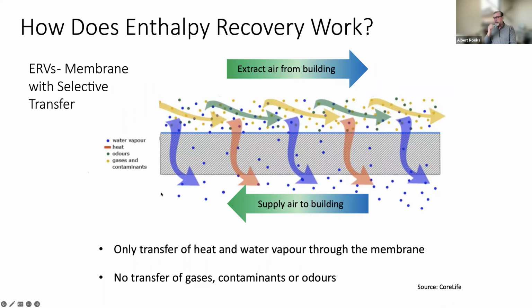The way the enthalpy recovery works is just like a Gore-Tex jacket. Upper right, we've got extract leaving the building. The extract is coming from the kitchen or bathroom, so it's got a slightly elevated humidity level, and the supply air to the building is dry coming in. And this is really in a heating climate. It's the reverse in a cooling climate, but it's the same thing. So up on the top side, you've got a high concentration of humidity, right? Little droplets of water, presence of humidity, and across that membrane, moisture can travel across, maybe not as a droplet. No liquid actually changes hands, more at the molecular level. Kind of like a Gore-Tex jacket where we keep sheets of water outside, but we allow moisture transfer to travel across.